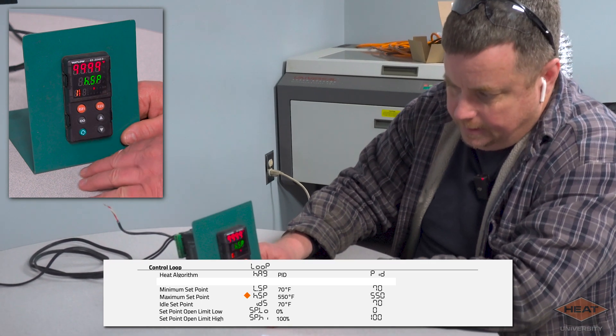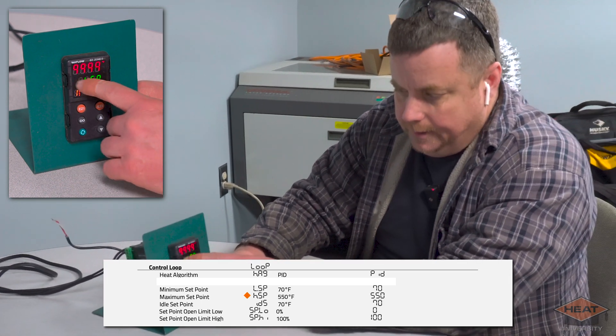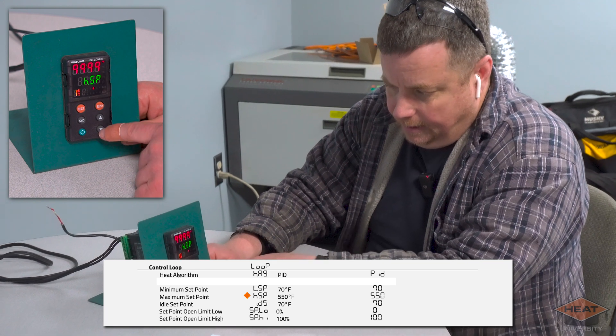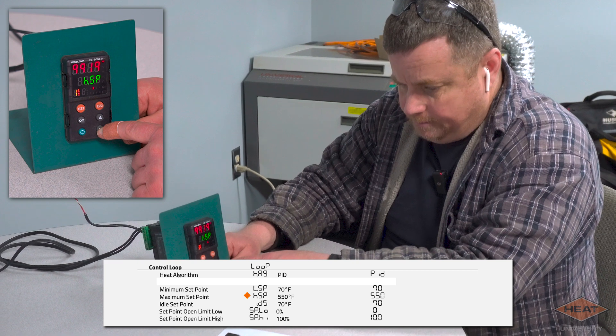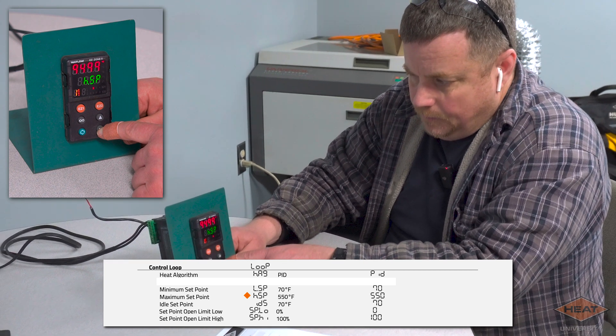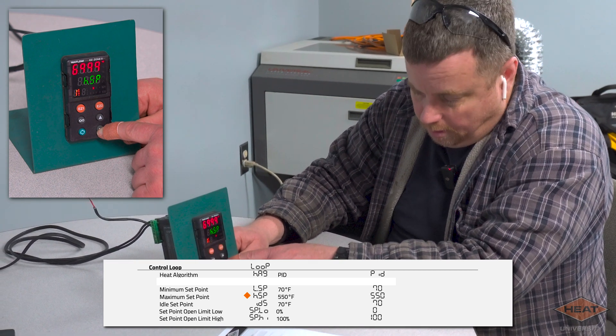Then we're going to cycle again, and then that's our high set point. You can see from the factory it's 999, and typically our high set point is 550 for an oil system, perhaps 250 for like a water glycol.